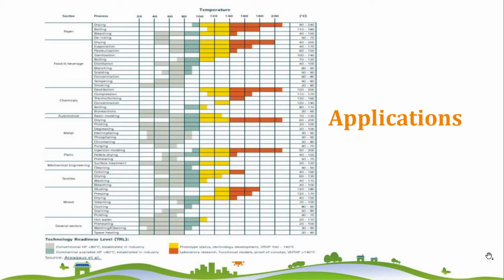And in the food processing industry, there are a lot of applications, including pasteurization, sterilization, CIP, and drying. In dairy industries, during pasteurization, the milk is heated from 4 degrees Celsius to 70 to 75 degrees Celsius, then immediately cooled down to 4 degrees Celsius. A centralized boiler is used to heat the system, and a chiller is used to cool it. Here we can have a CO2-based heat pump system, which supplies both heating and cooling for milk industries.